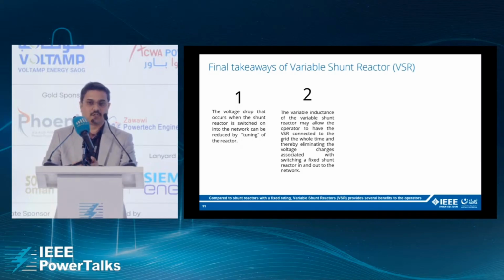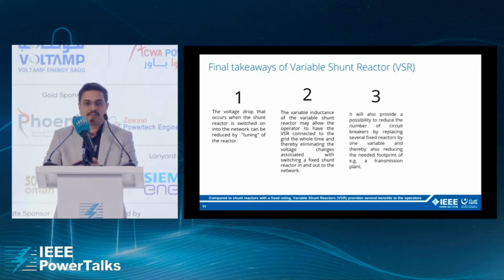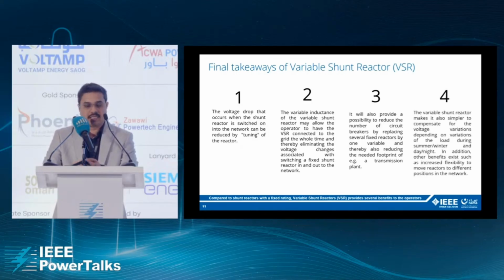So with the variable nature of the shunt reactor, you have more confidence and more flexibility to integrate more and more renewables in the system. Then, with a VSR, that is a variable shunt reactor, you do not need a very complex structure of breakers and a large transmission substation, which demand capital investment, because here, with just a reactor and a tap changer, you are able to generate equipment which is flexible enough to adjust itself to the flexible requirements of the transmission system.